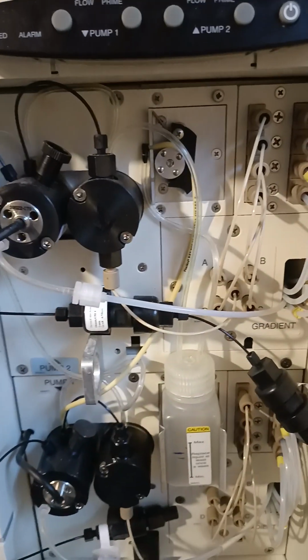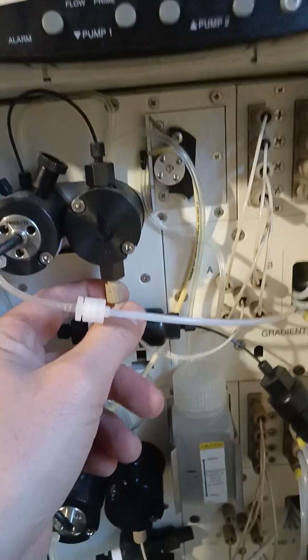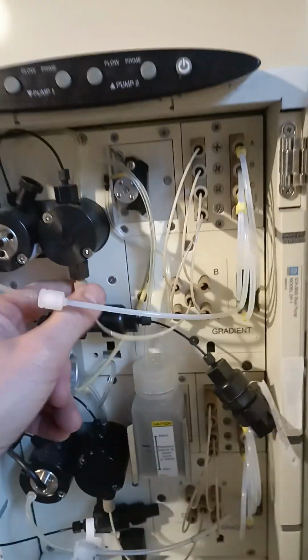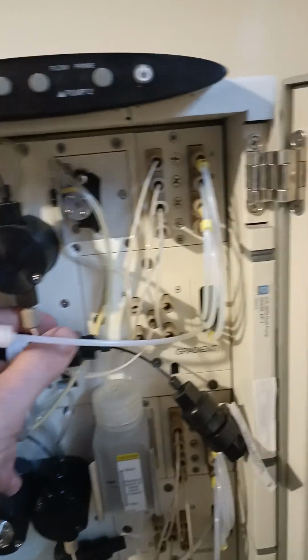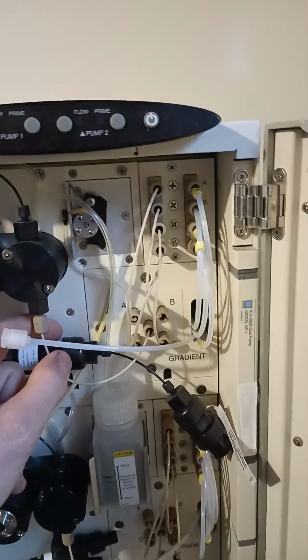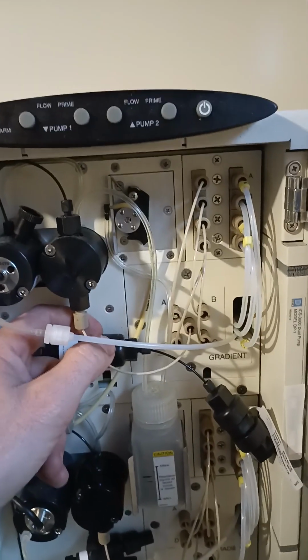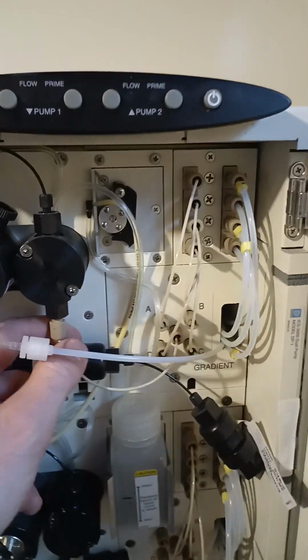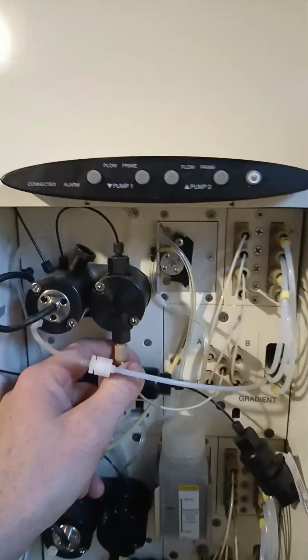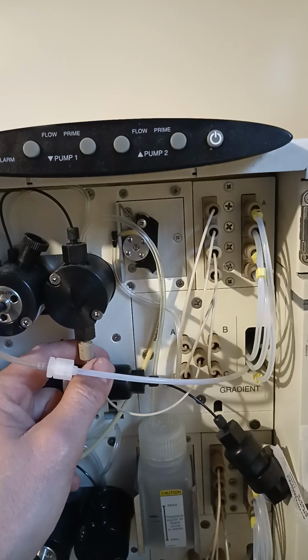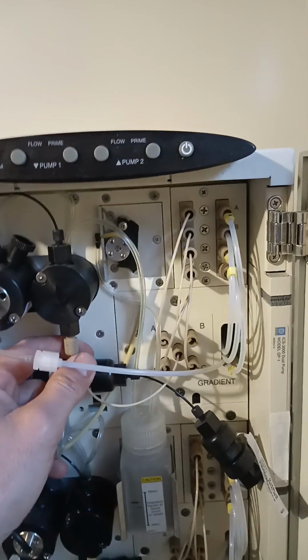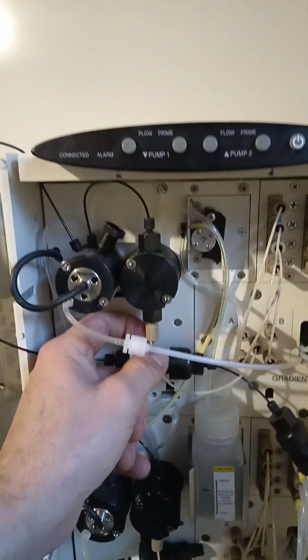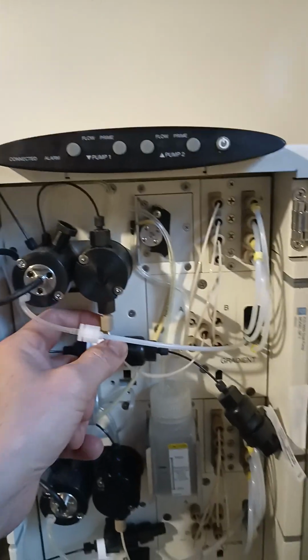We have our piston seal rinse here. This is to rinse the back end of the pistons as they retract out of the piston seals. That's a drying zone in contact with atmosphere. So if you're pumping any sort of salts, hydroxide, methylsulfonic acid, anything like that, you're going to experience salting on the piston. And then when it drives back through the seal, you're going to get scratching and premature damage on that piston seal.